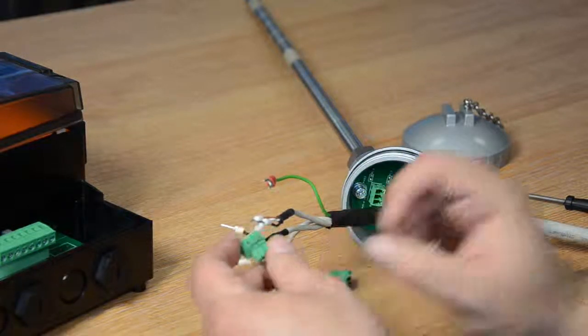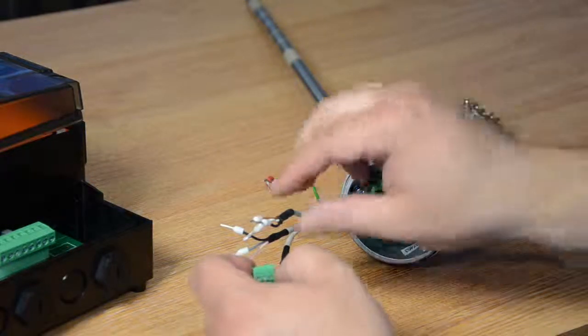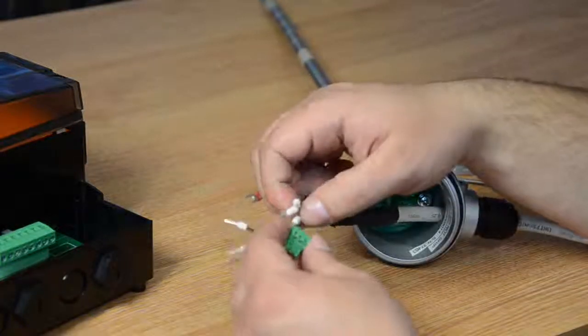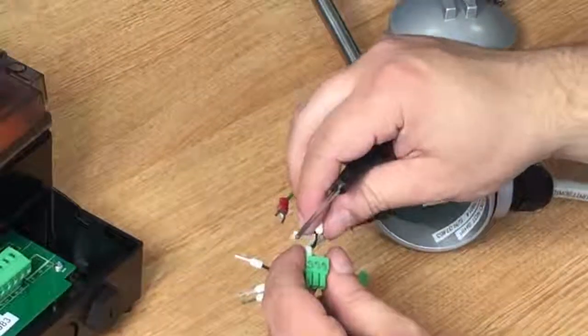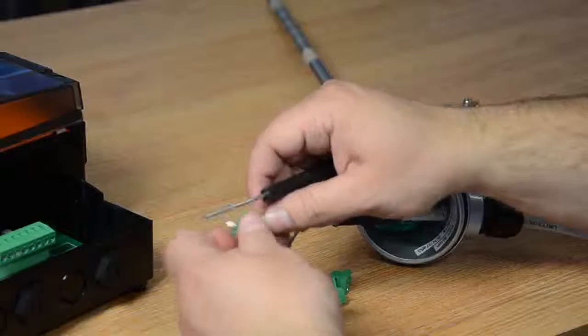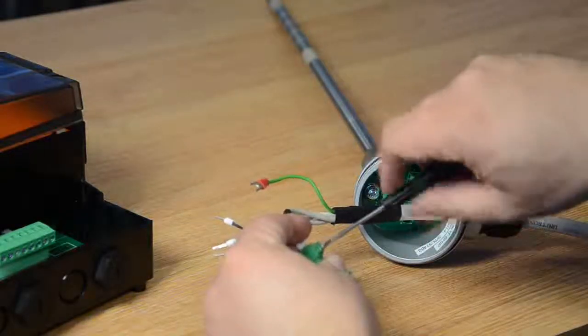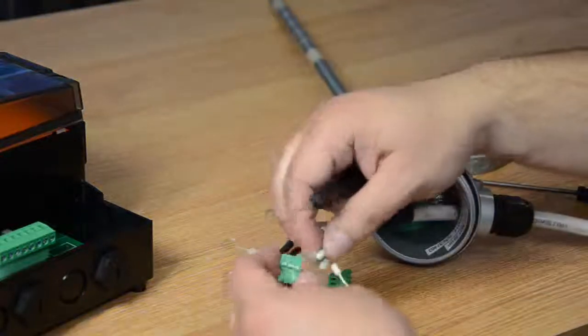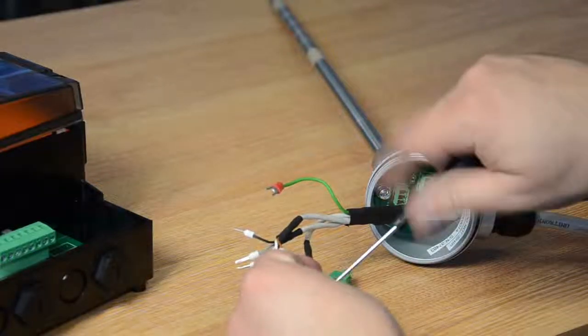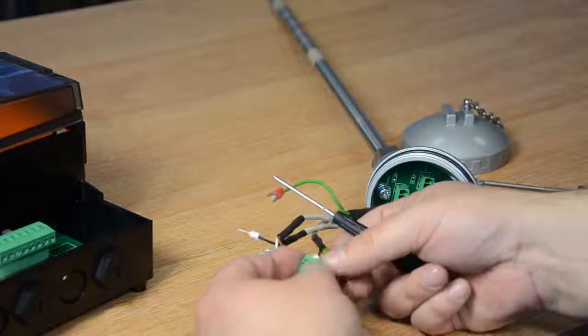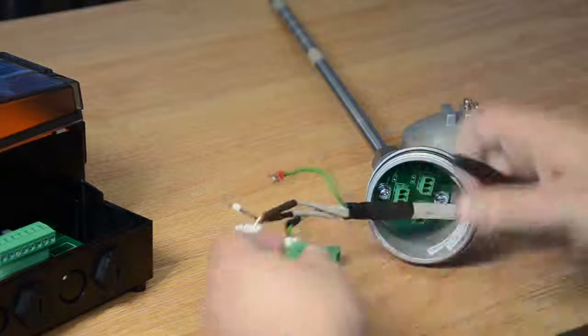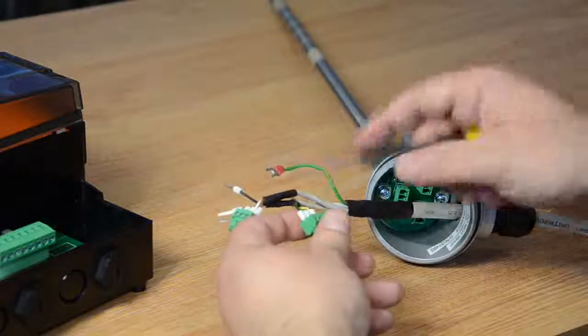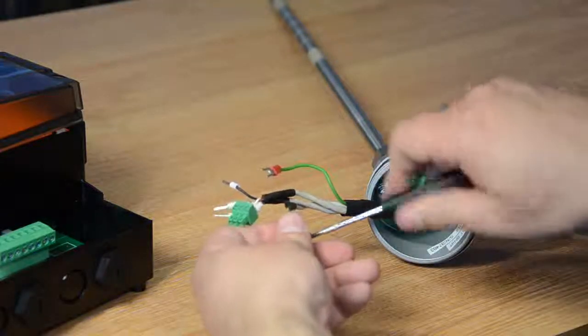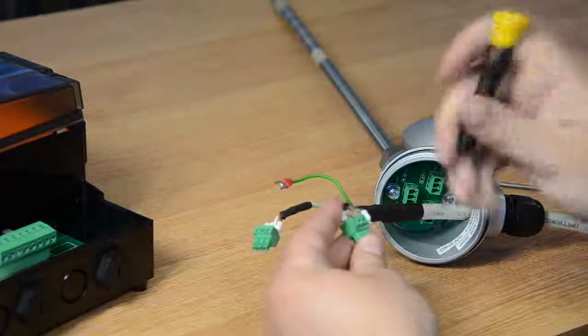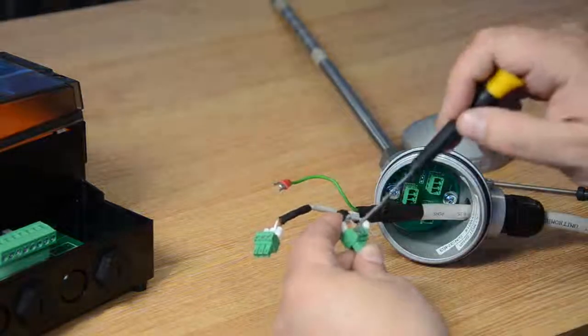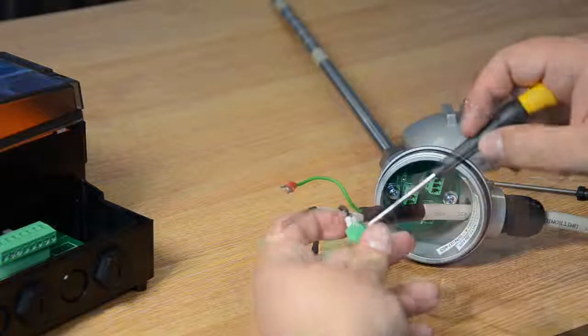So we'll start first of all with sensor point 1, which was our brown, black and white cables. So I'll insert our black cable into the left hand side, and then I'll put our test, which is our white cable, into the middle, and finally the sense, which is the brown, goes on the right hand side. For the second sensor, we will go to our green and yellow cable. Once more, black on the left. Your test, which is your green, goes into the middle. And your sense, which is our yellow cable, goes on the right hand side. Once more, all of these are from when you're looking at the screw side. So finally our third point, which you'll only have on 3-point probes. Black on the left, grey, which is our test, in the middle, and pink, which is our sense, on the outside.